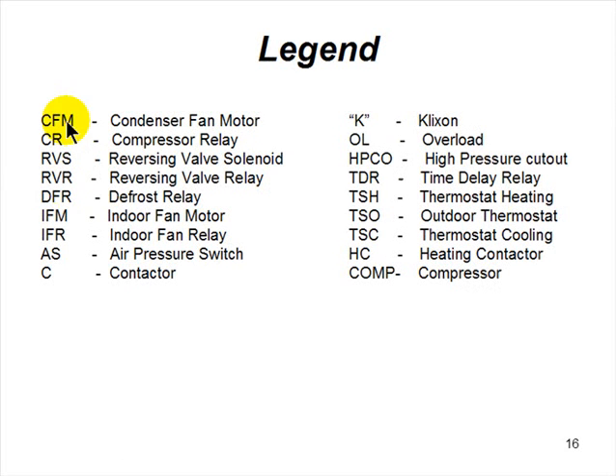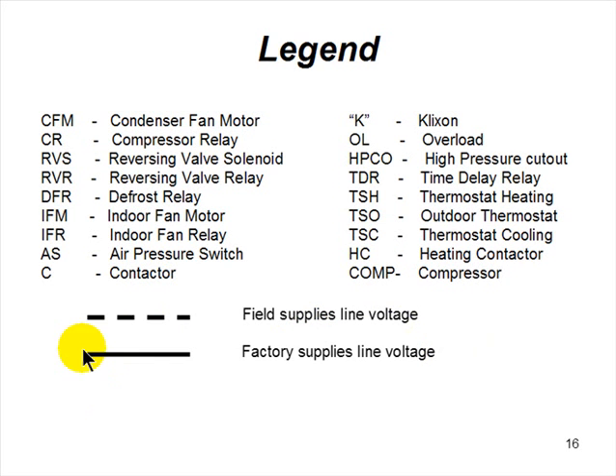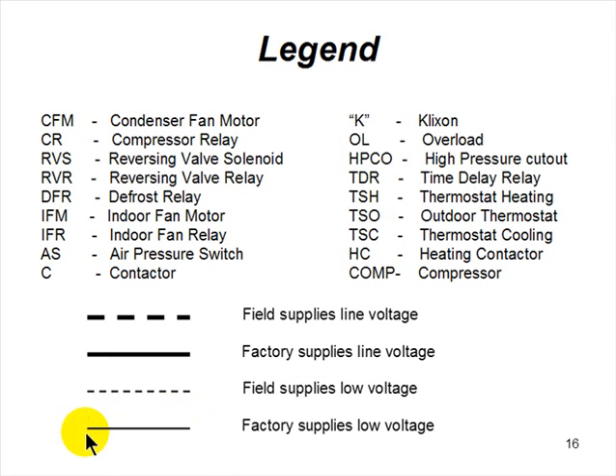If I didn't know what RVR was, I go to the legend. And the legend, they're going to ask you about in a test, defines all that stuff. RVR is reversing valve relay. RVS is reversing valve solenoid. This heavy dashed wire is field supplied line voltage. This solid one is factory supplied line voltage. Low voltage field supplied is a light dashed wire on the schematic, and the solid wire you see in the schematic is factory supplied low voltage, but it's thinner than the line voltage. They're going to ask you about this in a test.